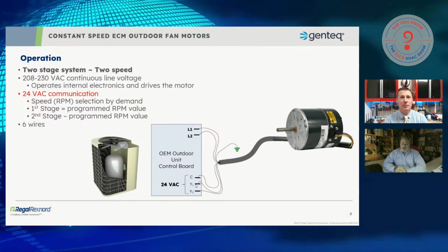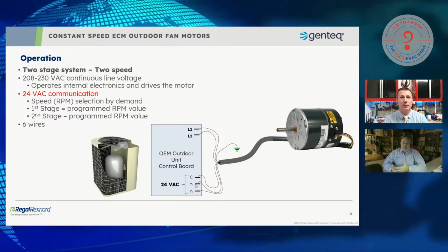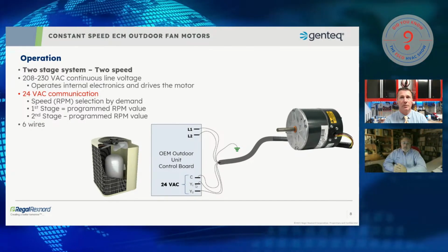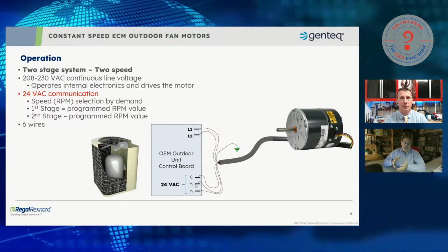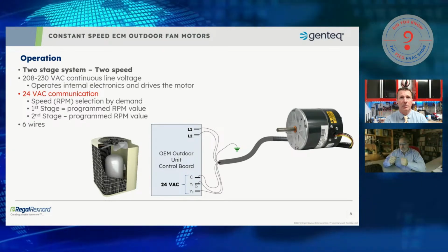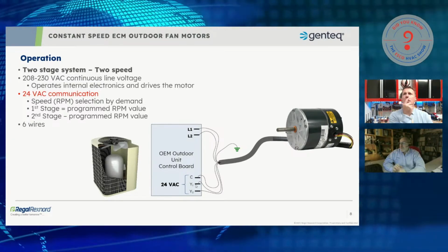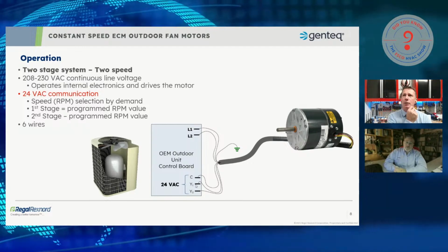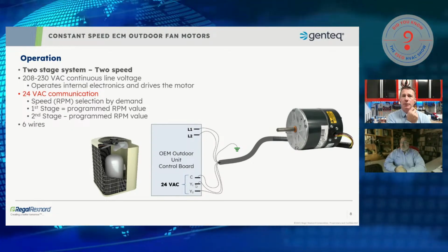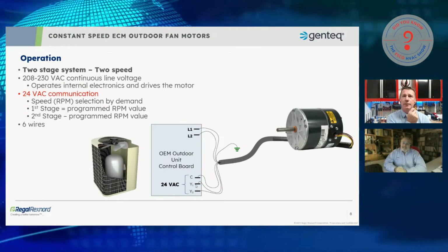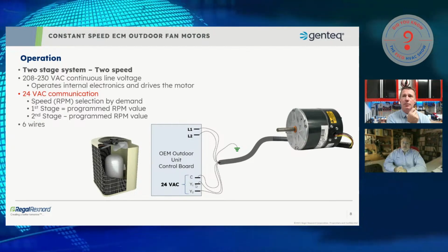So that's another reason you need to get into the OEM manuals and find out, should I see voltage on both when I get to two-stage, or should I see voltage only on the second speed? But again, these are just 24-volt AC wires, and the speed that the motor operates at is dictated by the manufacturer of the appliance.